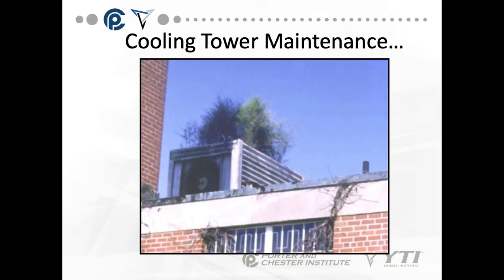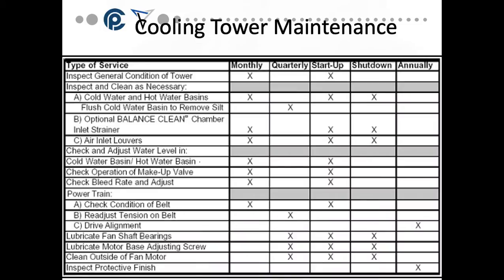Okay, so when you take a look at cooling towers on top of buildings, there's certain things that we're really looking for. For operations under severe conditions or during winter weather, it strongly suggests that the frequency of equipment inspections be increased, focusing on those components that are most affected by the increased stressors. Look for ice during winter operation. Look for additional evaporation during extremely hot months.